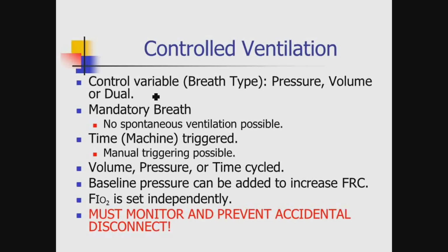So again, the breath that is being delivered, whether it is pressure-oriented or volume-oriented, doesn't matter. Again, it's a mandatory breath, no spontaneous. So can I have somebody in controlled ventilation with pressure support? No, because there are no spontaneous breaths. How is it triggered? Well, it's triggered by the machine. It's time triggered. What starts the breath is the respiratory rate control saying, hey, 5 seconds have gone by at a rate of 12. Time for a breath.